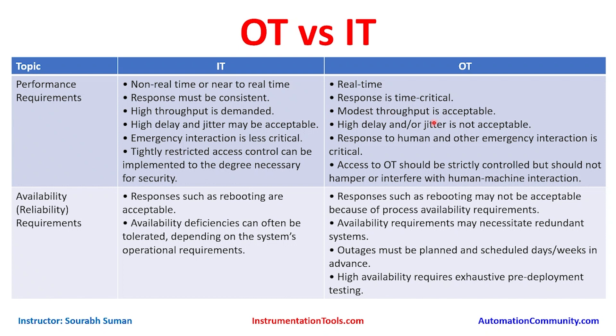Simple commands consume very little bandwidth in OT. In IT, a jitter delay might be acceptable, but in OT, delay or jitter is not acceptable. If jitter occurs, a digital input could flip two or three times, and since these systems read data in milliseconds, the system may interpret that as five or six separate commands. Any delay could cause a valve or actuator to operate at the wrong time, resulting in production losses.